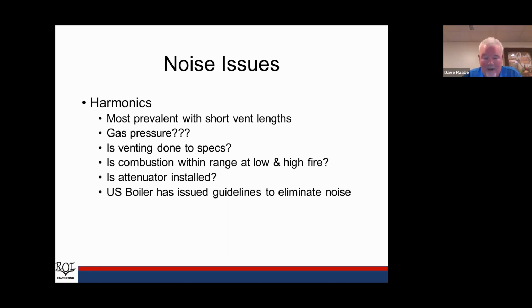Talk a little bit about noise issue. We've run into a few of these. Harmonics might sound like a foghorn. Usually when the boiler first lights, it might make that, and then as it ramps up, that kind of goes away. It's more prevalent with short vent lengths. Some of the things you need to look for: gas pressure. Do we have sufficient gas pressure? Is our venting installed as per the book? Is it within specs? Is our combustion within range at low and high fire? So we want to check that. Is the noise attenuator installed? And I'll show you a slide on that coming up here.